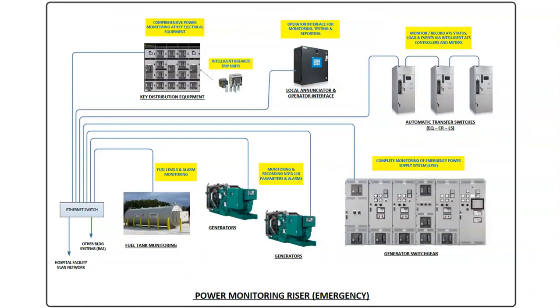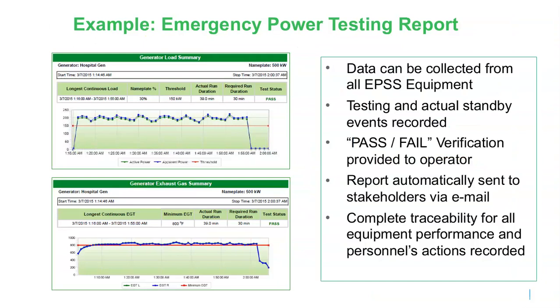When you're looking at which equipment gets brought in, it's what we reviewed already, but just for a quick look again: we're looking at the generators, the main power distribution from those generators, the transfer switches, and then you may want to bring in, again, your fuel systems, potentially your batteries. And if you've got some local annunciation, many times it can be very helpful to have access to that information as well. All of it should be networked into your system so that, either at the facility or even in some cases remote from the facility, a power monitoring system is capable of capturing the information gathered by the meters and then returning the reports that can be used for the documentation, but also can be used to make sure that everything was done correctly and identify if there were any other vulnerabilities.